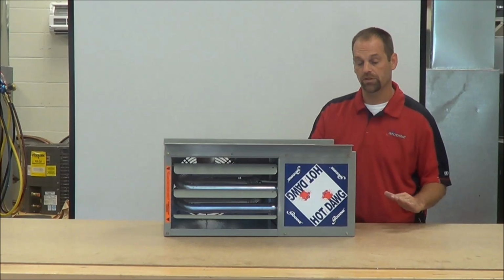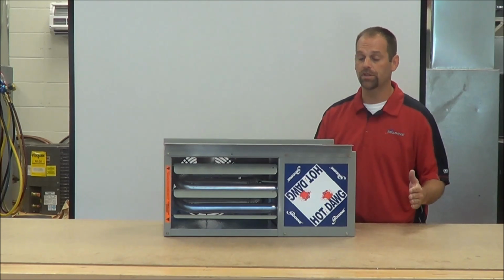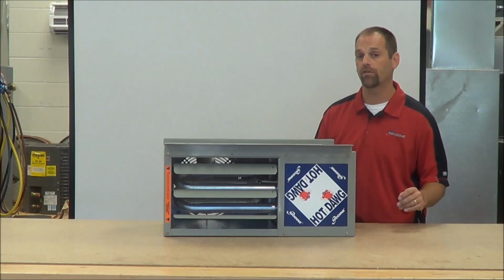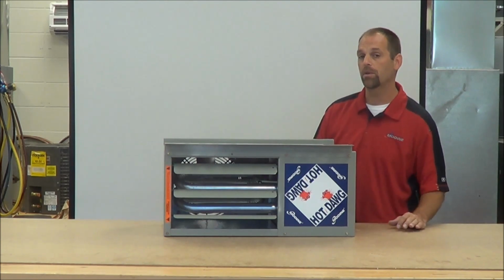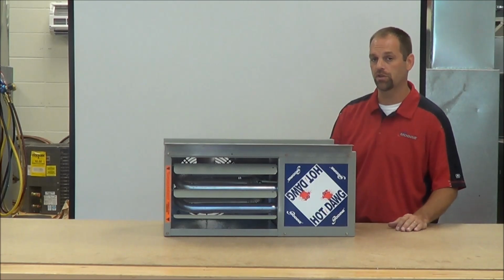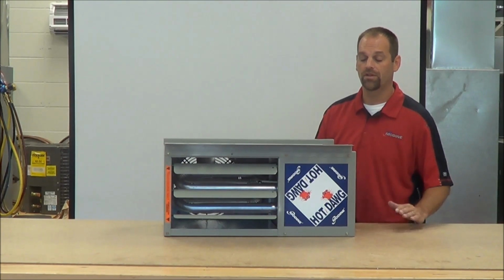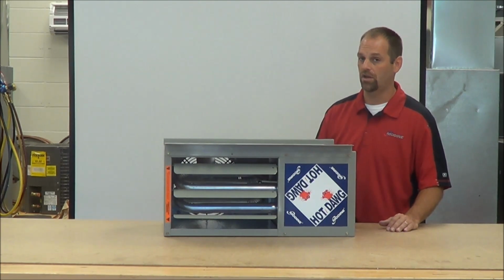what to look for. The first thing you have to do is, if you come to the unit and it's not functioning, it's dead and you have your thermostat calling for heat, you want to check your incoming power to make sure you have the proper voltage to the unit. If you do, the next step would be, let's check the transformer.